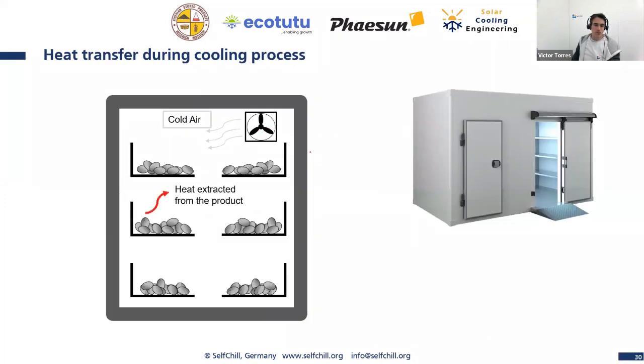Okay, so we have already our first calculation, the energy extracted to cool down 500 kg tomatoes in the cold room. Thank you very much, Charles. 4.7 kilowatt hour is what we need. We will write it down. 4.75 kilowatt hour is the energy we need to cool down 500 kg tomatoes from 20 degrees to 10 degrees. If this is happening every day, then this is the cooling load every day.